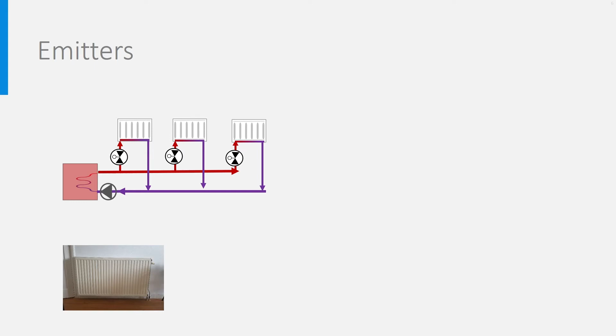There is in general a central thermostat controlling the heater and the circulation pump. The thermostat is often placed in the living room and controls therefore the temperature in the living room. So the temperature in the other rooms will be different. That's why there are valves on radiators, either simple ones with manual control of the flow like this, or thermostatic valves controlling the flow based on the measured air temperature close to the radiator, like that. The temperature sensor is part of the valve. The set point temperature depends on the number chosen on the valve.